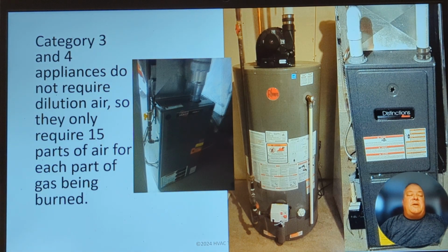Now, category 3 and 4 appliances do not require dilution air because they have fans that assist in pushing the air through either the heat exchanger or the vent system, or a combination of each. They don't require dilution air. So even if we're collecting the air out of the room itself, we only have to account for half as much air, just for the combustion process.